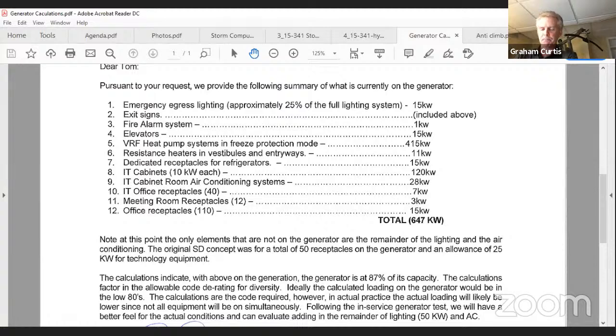There was some confusion recently about the load test and what the capacity was. It wasn't a limitation on the generator. It was a limitation on the ability to test the generator thoroughly, because there was not much load. It was not a hot day, there wasn't much air conditioning running, and the contractor didn't have a large enough load bank to really put this thing through its paces. But there was no problem; it is more than adequately sized to handle the life safety loads for the building.